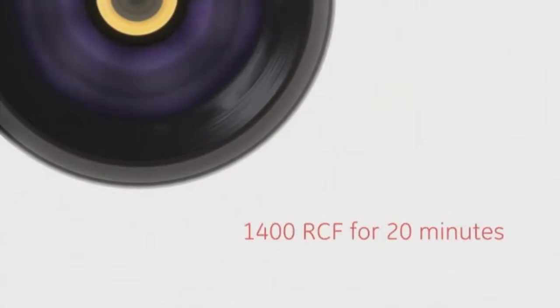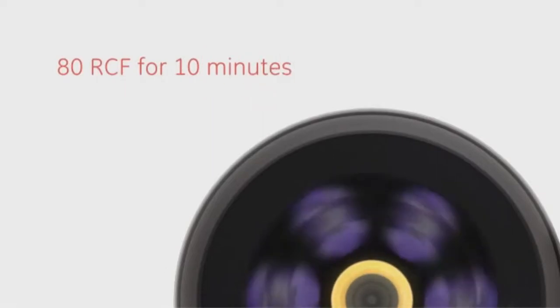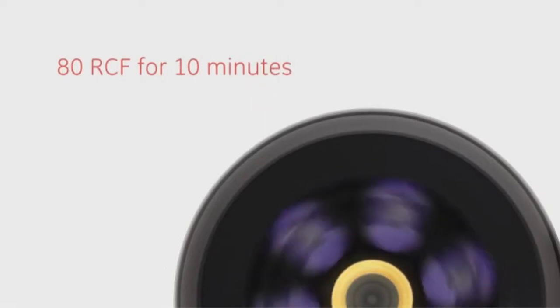High-speed spin should be performed at 1400 RCF for 20 minutes. Low-speed spin is then carried out at a setting of 80 RCF for approximately 10 minutes. Consult your centrifuge operator manual for the proper RPM setting.